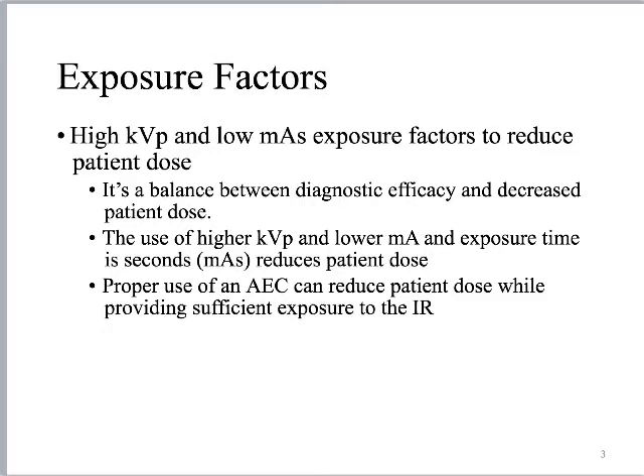Proper use of an automatic exposure control device should reduce patient dose while still providing an appropriate amount of exposure to the image receptor — assuming we're using the AEC properly. Improper use of the AEC could result in increased patient dose. Additionally, as we increase beam filtration, we are often reducing patient skin dose. As we filter the beam more and more, we're reducing the low-energy x-rays that would just ionize the patient's skin and stop there, providing no diagnostic information.